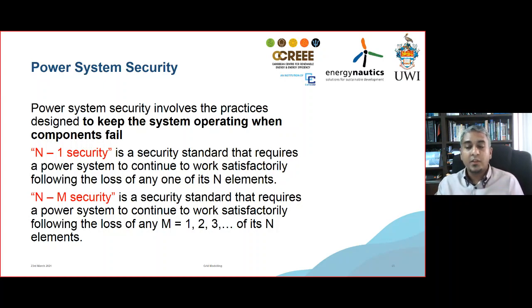The standards you employ vary across regions and regulators, but the concept remains the same. You may have N-M security, or normally N-1 security, which means that for a power system to continue working satisfactorily, if one element is lost, the system must continue — hence N-1.